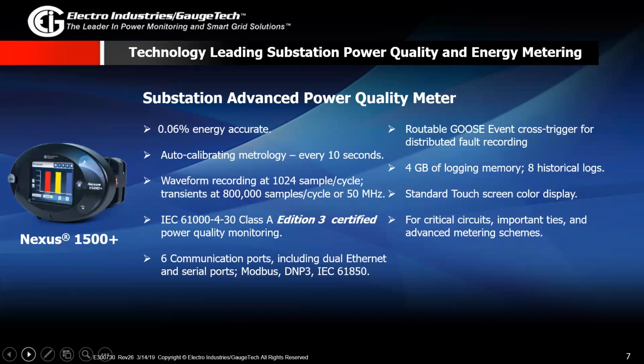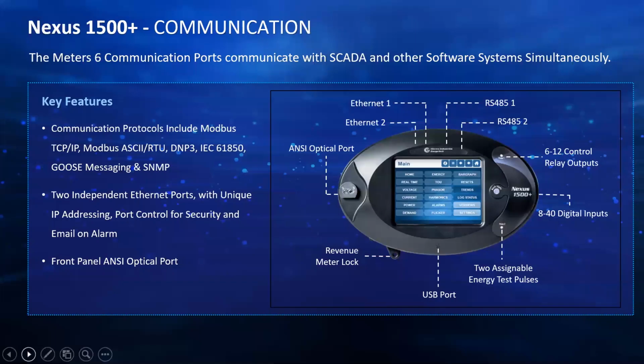This is again showing the communication options that are available on the front plate of the Nexus 1500 Plus. It has up to 2 RS-485 ports, again, up to 2 Ethernet ports, which you can assign separate IP addresses to. There's a front ANSI optical port, and you can also choose to have controlled relay outputs, digital inputs capability with the meter as well. So you can collect pulses from other entities and aggregate them into the meter. And like I mentioned before, in addition to Modbus and DNP3, this meter is compatible with IEC 61850 and can do GOOSE messaging as well as SNMP.